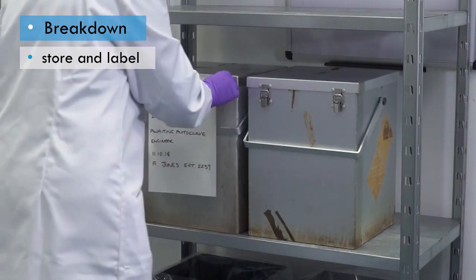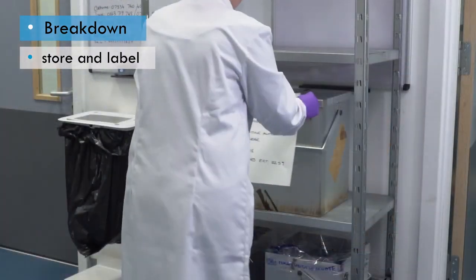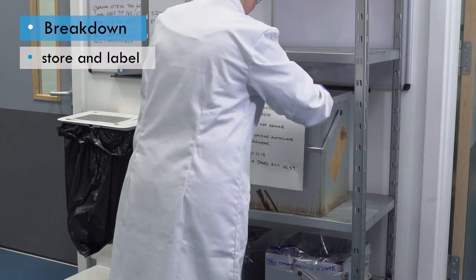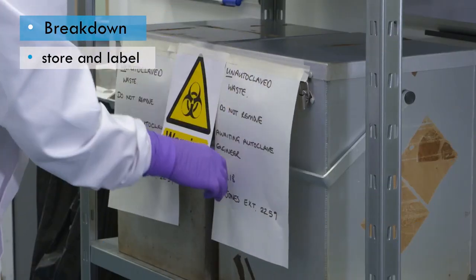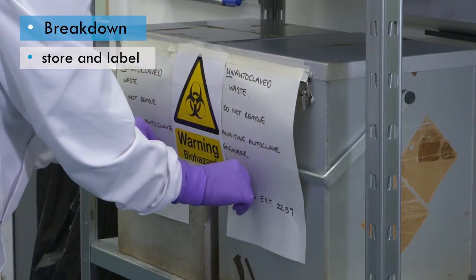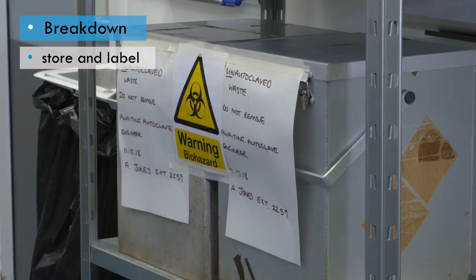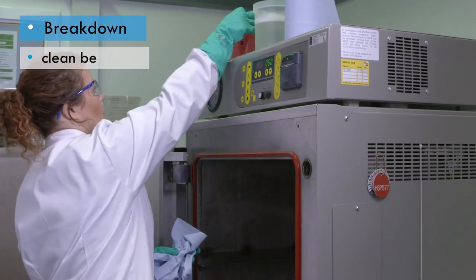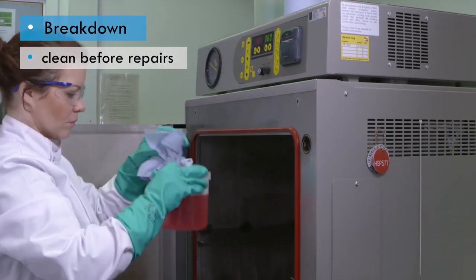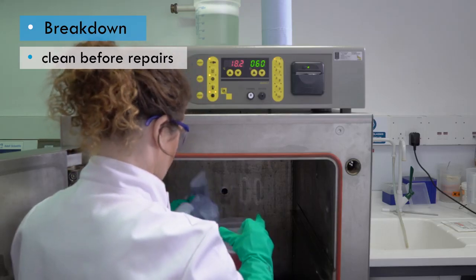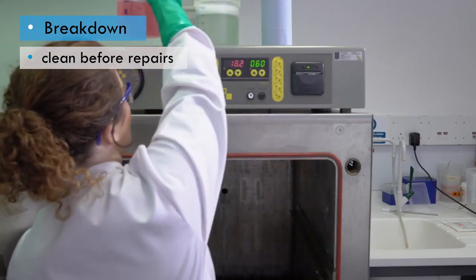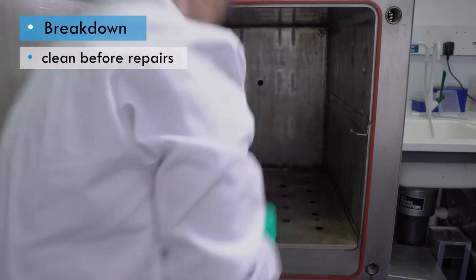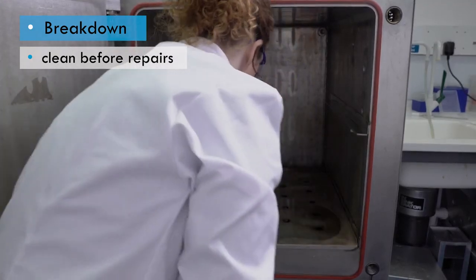If the waste needs to be sent elsewhere for sterilization, it will need to be suitably packaged for transportation in accordance with the UN model regulations. Once the waste has been removed, if access to the autoclave chamber is required for maintenance or repair, the inside of it should be wiped down with an effective disinfectant.